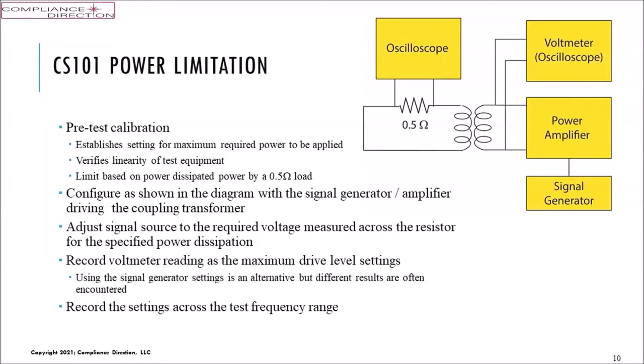Other folks have hooked up automated systems where they control the voltage at the signal generator output. Now, sometimes they'll do this without providing feedback. So if I do this during the calibration and the test is a low impedance circuit, I can overdrive heavily because the signal generator will push a lot of voltage or a lot of current. So the idea is to current limit.